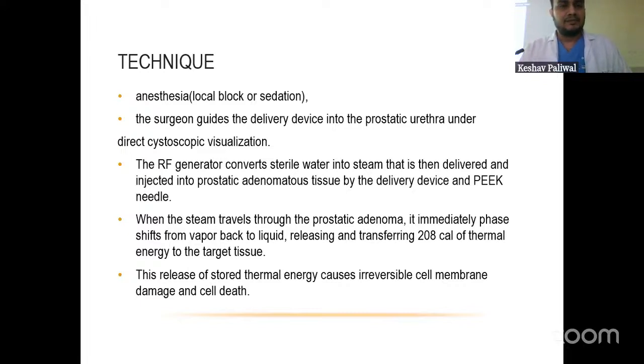In the technique, it can be done under local block or sedation. The surgeon guides the delivery device into the prostatic urethra under direct cystoscopic visualization. The radio frequency generator converts sterile water into steam that is then delivered and injected into prostatic adenomatous tissue by the delivery device and PEEK needle. When the steam travels through the prostatic adenoma, it immediately phase shifts from vapor back to liquid, releasing and transferring 208 calories of thermal energy to the target tissue. This release of stored thermal energy causes irreversible cell membrane damage and cell death.